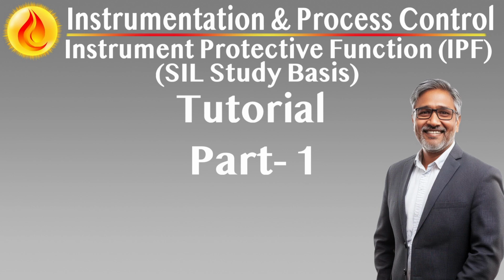Hierarchy and functional integrity in safety instrumentation. The classification of an IPF reflects its functional criticality and performance expectation within the overall safety strategy. This includes specifying the initiating event, what triggers the IPF, the protection logic, how the function operates, the final element, what action it enforces, the response time and diagnostic coverage, how quickly and reliably it works.